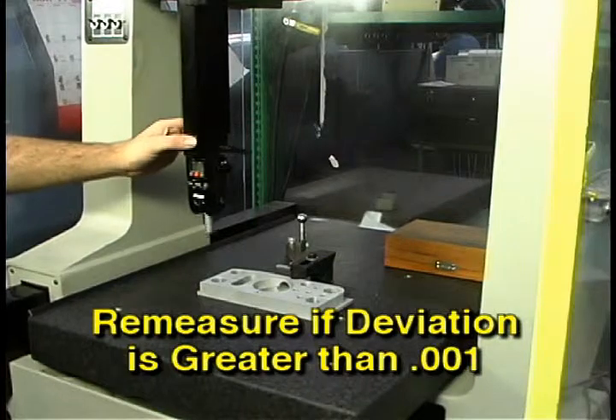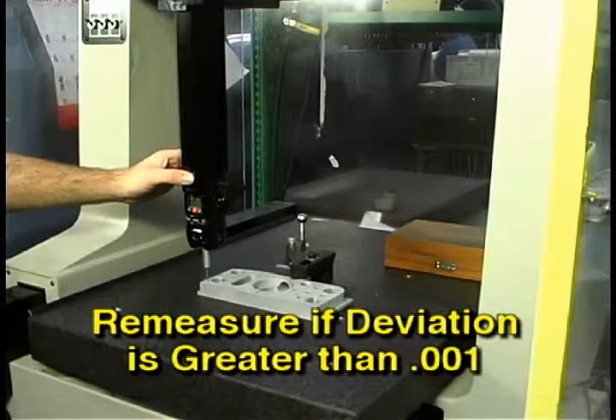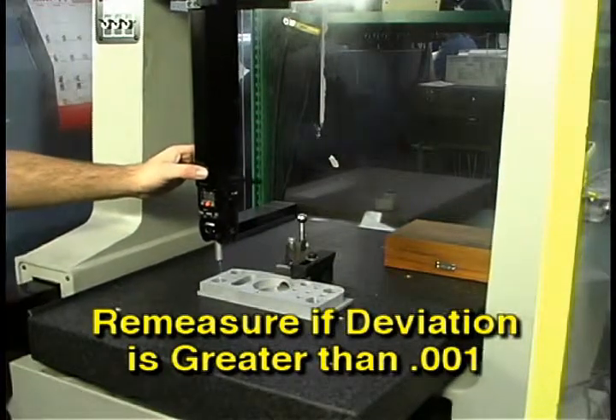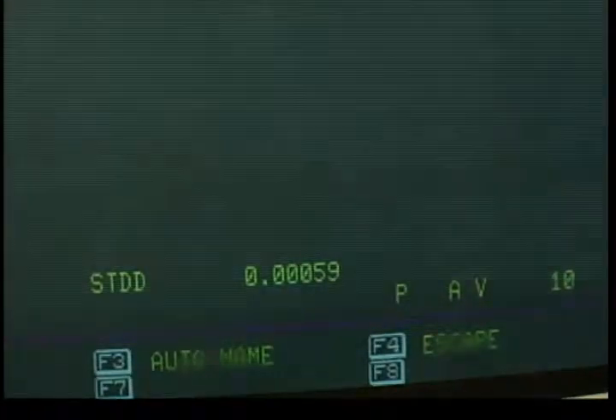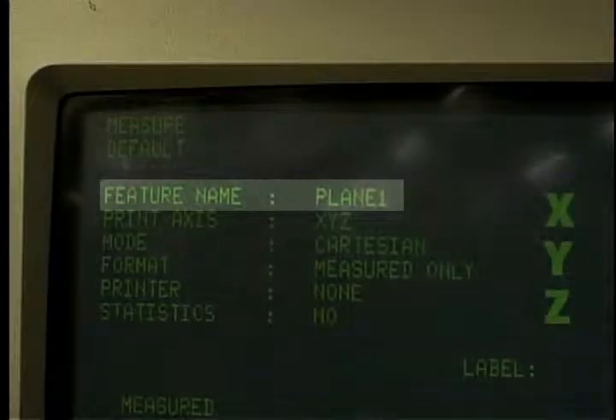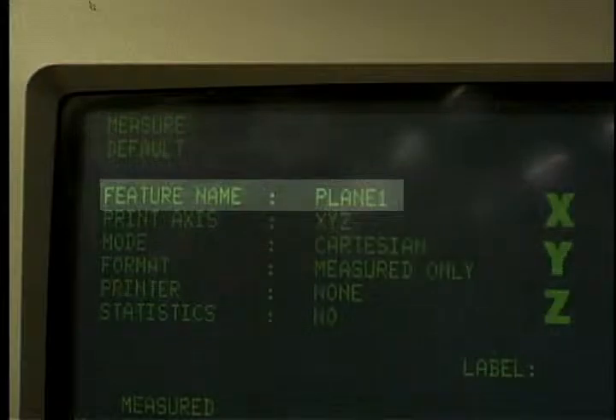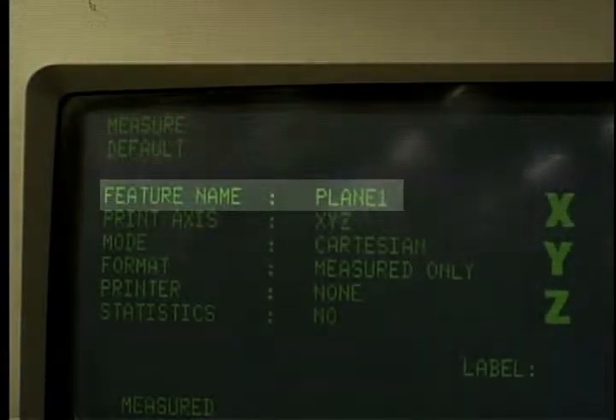If the deviation were more than a thousandth, the surface should be re-measured to make sure the surface is flat within tolerance. In the menu at the bottom, click on Auto Name to store the value as Plane 1. The Plane 1 name and the value stored with it can now be recalled when the alignment is performed.